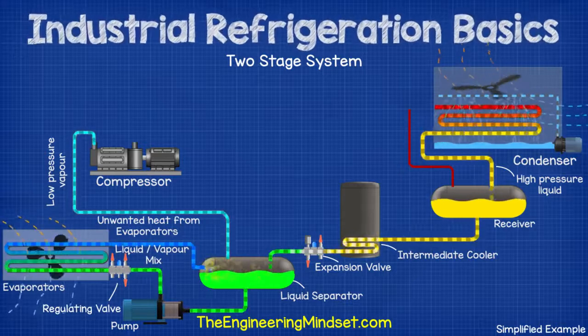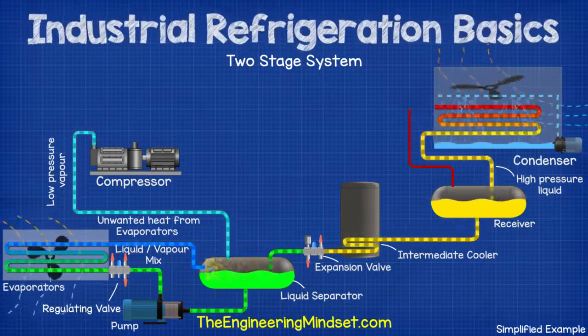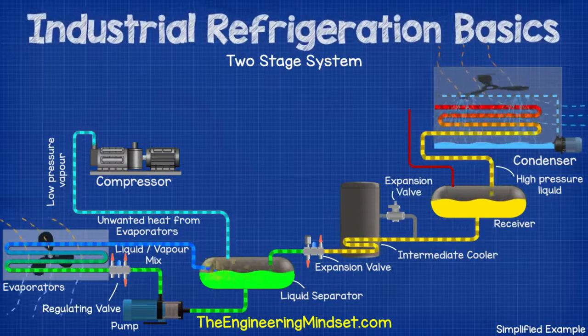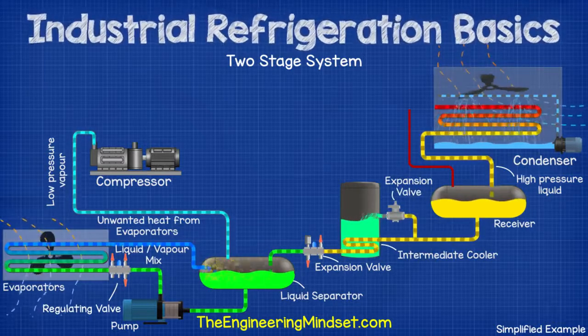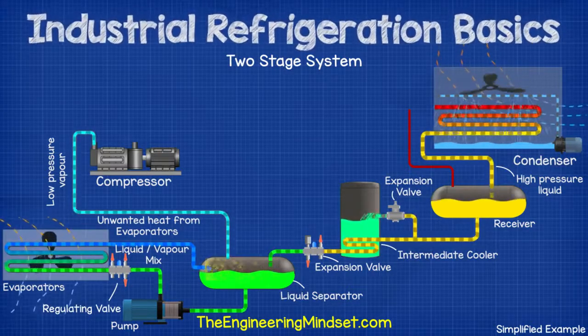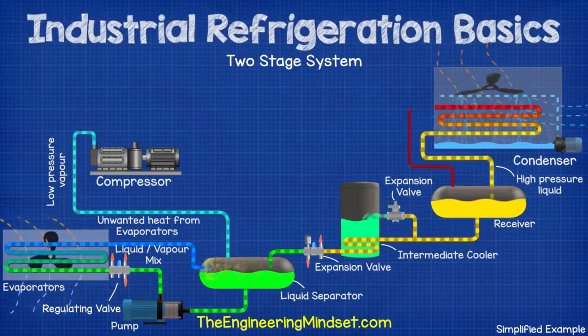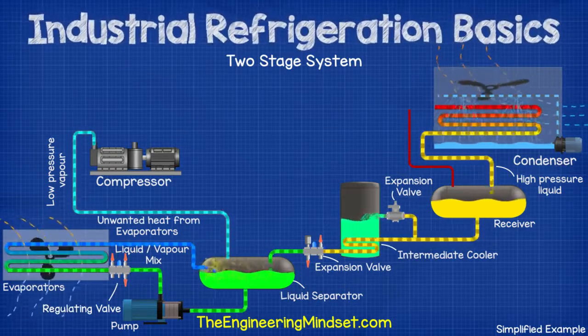It then continues its flow via the separator, the evaporator, and back to the separator. Another stream of refrigerant comes off the main line and is sprayed into the tank by an expansion valve to produce a cooling effect. As it is sprayed and evaporates into the tank, it cools the submerged coil, which sub-cools the main flow of refrigerant inside the coil before it flows to the main expansion valve.